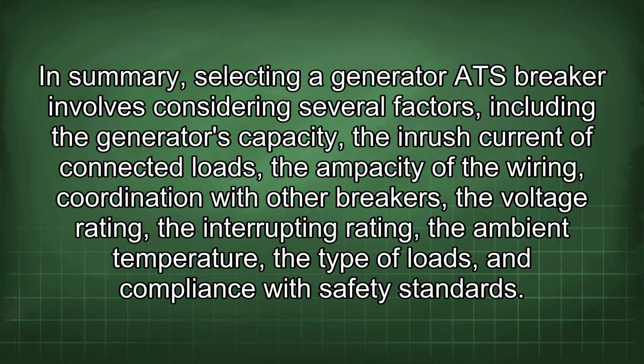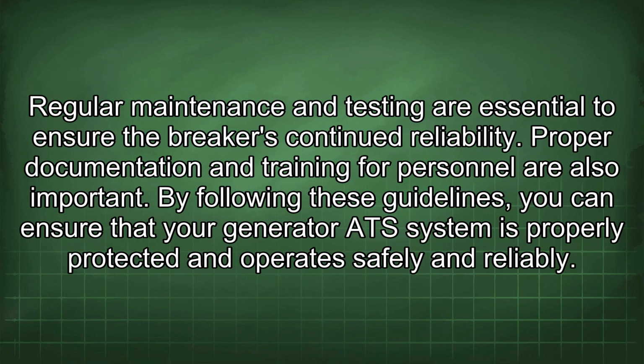In summary, selecting a generator ATS breaker involves considering several factors, including the generator's capacity, the inrush current of connected loads, the ampacity of the wiring, coordination with other breakers, the voltage rating, the interrupting rating, the ambient temperature, the type of loads, and compliance with safety standards. Regular maintenance and testing are essential to ensure the breaker's continued reliability. Proper documentation and training for personnel are also important. By following these guidelines, you can ensure that your generator ATS system is properly protected and operates safely and reliably.